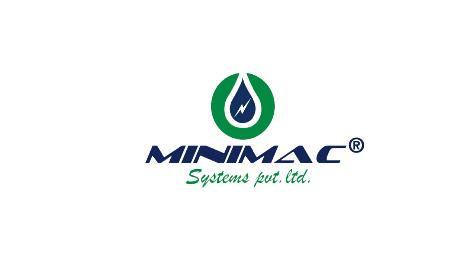There is no point in checking the quality of booster oil lubricant. It should be replaced in 3 months. That is the fact, because it has a reservoir of 1.6 liters. So apart from the checking and condition monitoring, it should get replaced every 3 months. Like that, it is optimized.